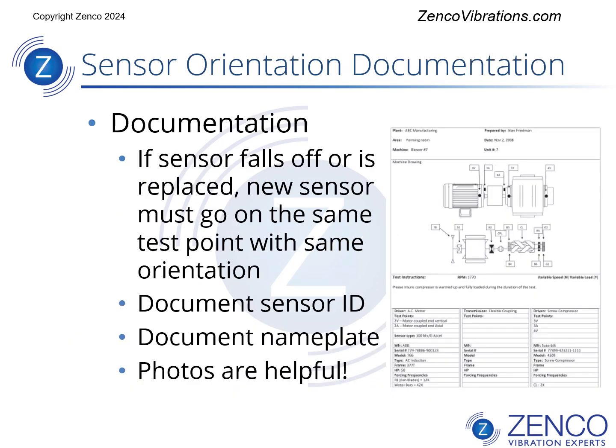It's good to record the sensor position on a machine test form. If a sensor falls off or it's replaced, the new sensor has to go in the same place with the same orientation. If you're doing a walk-around program, this would tell the person taking the reading exactly where to take it and how to orient the sensor. Not only that, you can document nameplate information on this, and photos are always helpful.